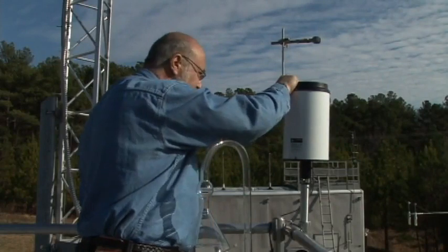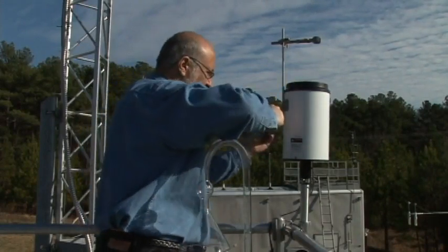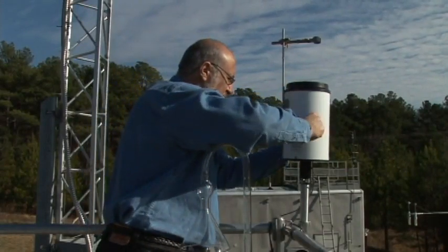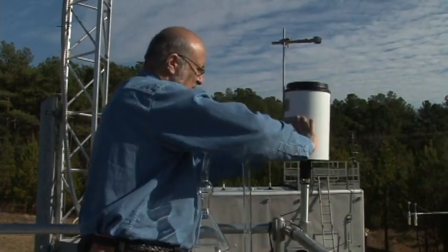You will need to calculate how many milliliters of water translate into millimeters or inches of rainfall. This information is in the manufacturer's operation manual. Once you have decided on how much water to introduce into the gauge, these will be the reference values for the calibration. The holding stand is now attached so that the burette can be positioned above the funnel opening so that water will drip into the funnel.